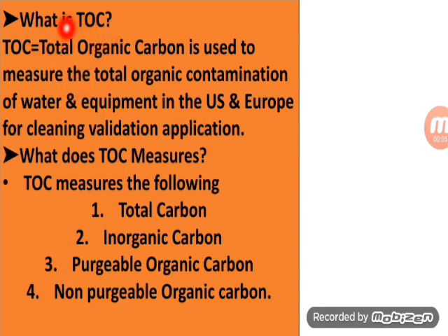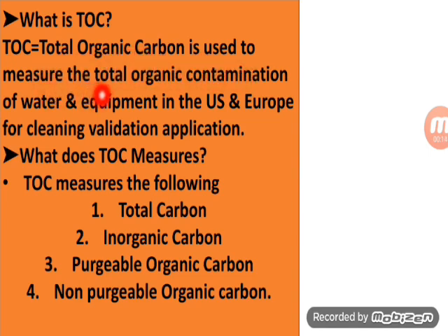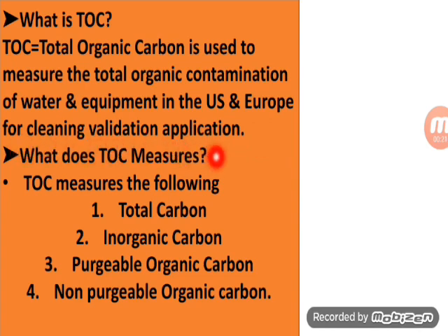The second question is: what is TOC? TOC means Total Organic Carbon. Total organic carbon is used to measure the total organic contamination of water and equipment in the pharmaceutical industry, particularly in the US and Europe, for cleaning validation applications.